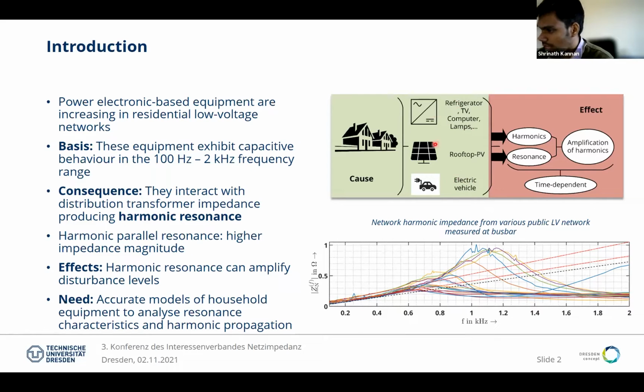All these have a prominent, or predominantly capacitive behavior in the frequency range from 100 Hertz, above the fundamental frequency, up till 2 kilohertz. What they typically do is interact with the distribution transformer's impedance, which is the medium voltage to low voltage network transformer, and they produce harmonic resonances.